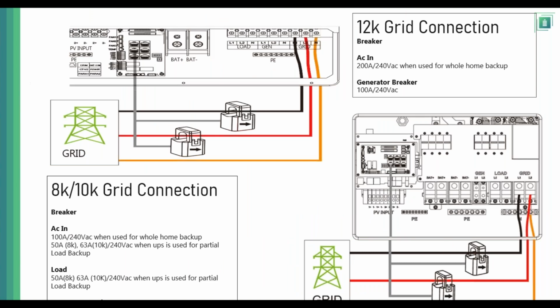And moving on, the grid connection for the inverter. So as we spoke, I showed you where the grid connections would be, and then the CTs that will go from grid to inverter, assuming whole home backup solution. That means that you have the meter, in between the meter and the main panel, you have the inverter, right? That's how you would do a whole home backup solution.